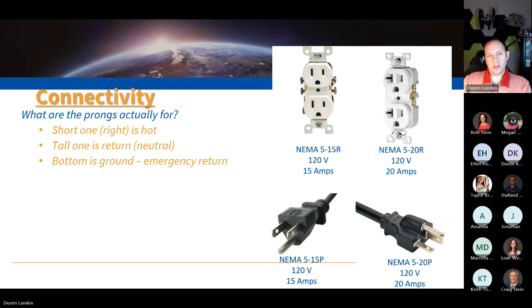Now, one big piece of this: just because it's got a 20 amp outlet, we have to make sure the wiring in the wall is good. You can't just take a 15 amp outlet and stick a 20 amp on it and call it good. There are different ratings for all the wiring behind it to make sure it's good. So speak with your local electrician first.